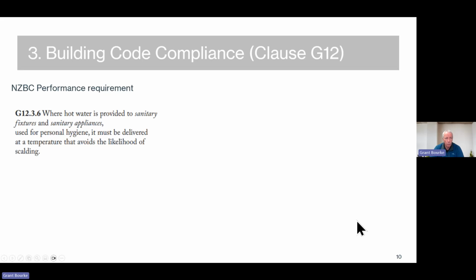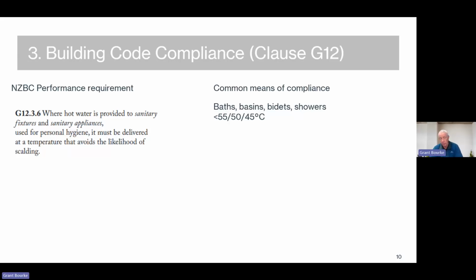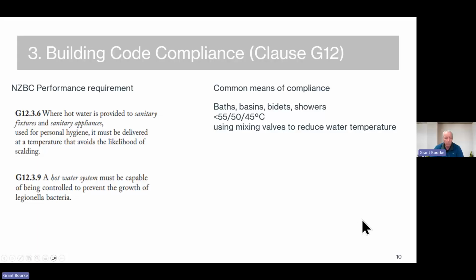So building code compliance, if we look at clause G12, we've got a couple of performance requirements. We've got 3.6, so it can't be too hot. How we go about that is obviously our sanitary fixtures for personal hygiene, depending on when the fixture was installed or whether you're at an installation with vulnerable people, we need to limit the water temperature, and we do that using mixing valves at the branch offtakes or for the whole ring main in order to reduce the water temperature. The second clause is preventing Legionella.